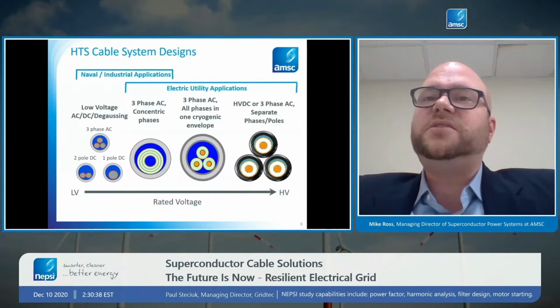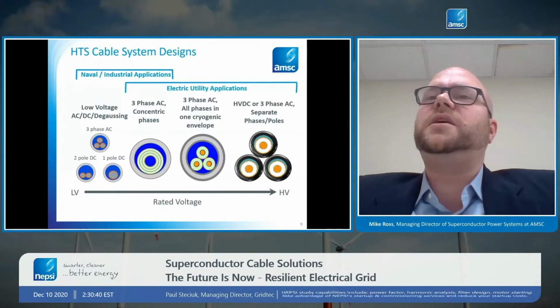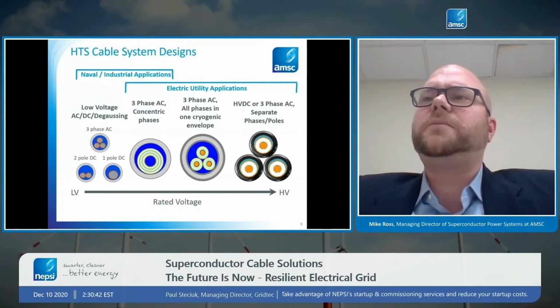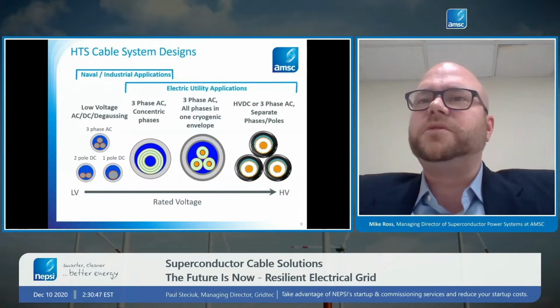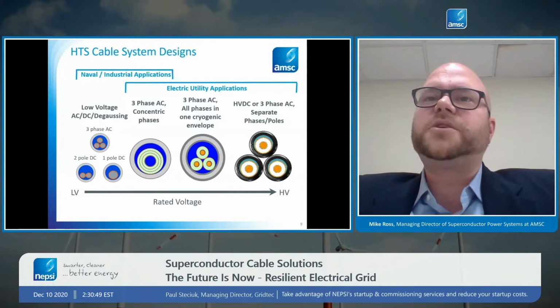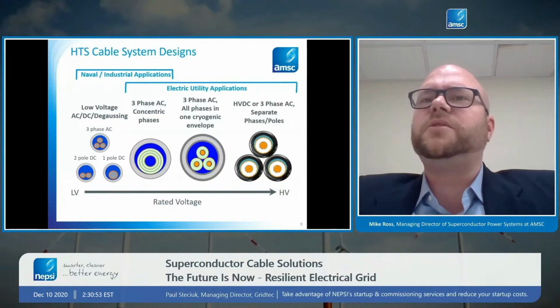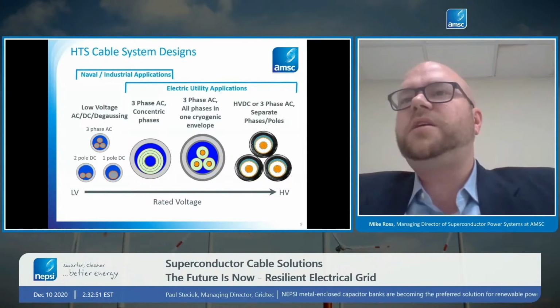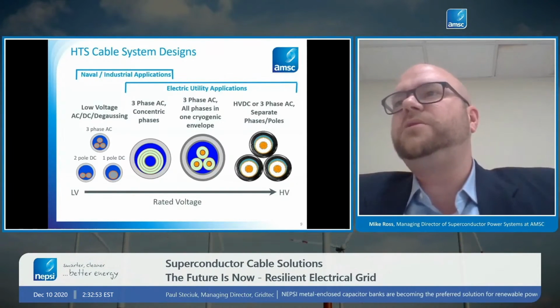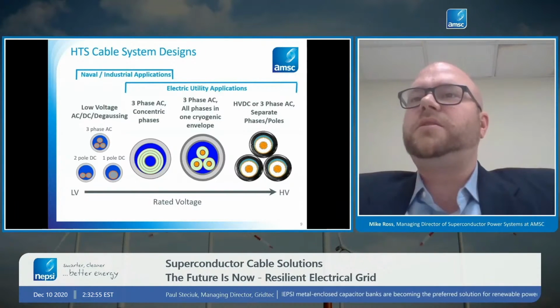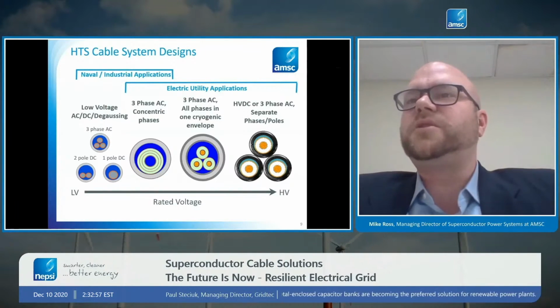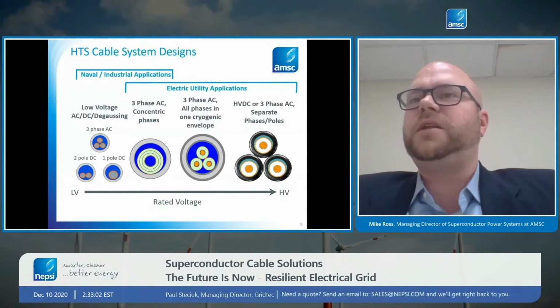Low voltage DC cables are commonly used in the data center world, where you're moving 48 volt DC, very large currents around a data center. Superconductor cables can replace those very large current cables. On the right-hand side here are the configurations that we use for utilities. The three-phase AC concentric phase cable is the most commonly used cable that we're looking at now.